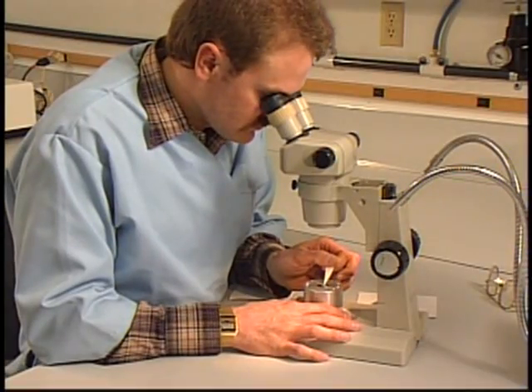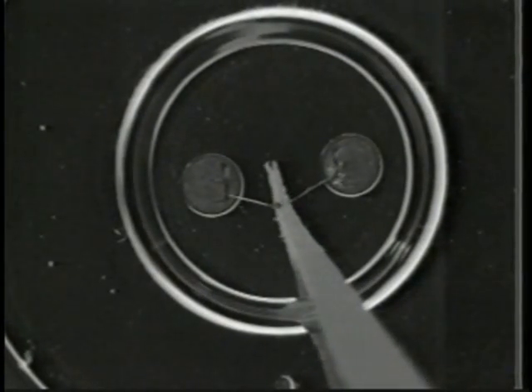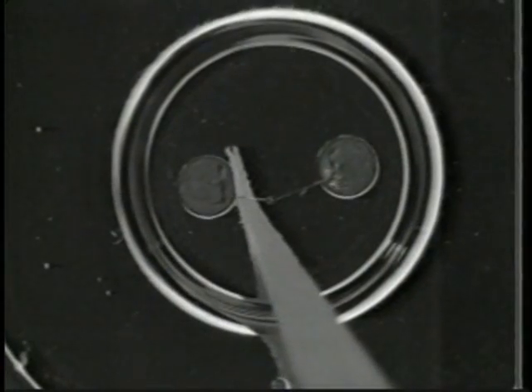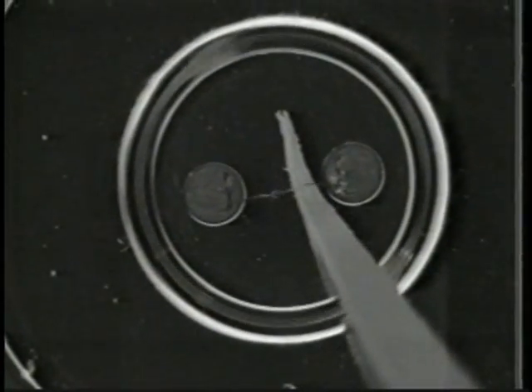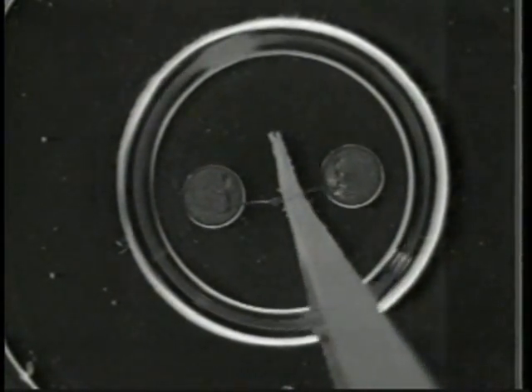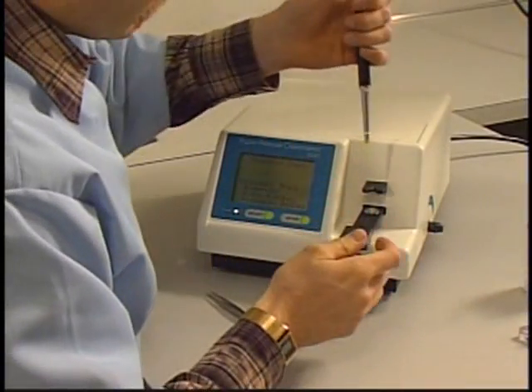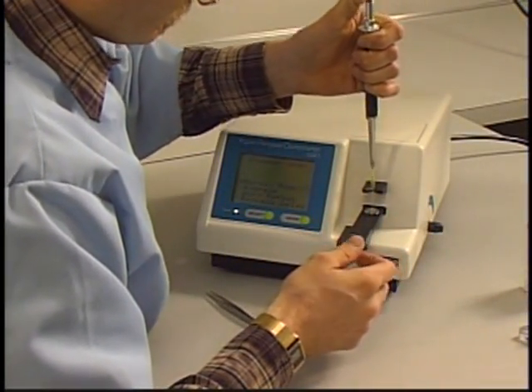Using a dissecting microscope or some kind of magnification, slide the narrowest part of your paper underneath the thermocouple and wiggle it back and forth until you arch it up and straighten it out. Now that the thermocouple is clean and healthy, you're ready to resume calibration. Remember, you can avoid the hard way. You can avoid the rigorous cleaning and the scrubbing if you simply perform a water rinse on a routine basis. Watch your thermocouple, clean it often, and then it'll be easy. You won't spend much time at it.